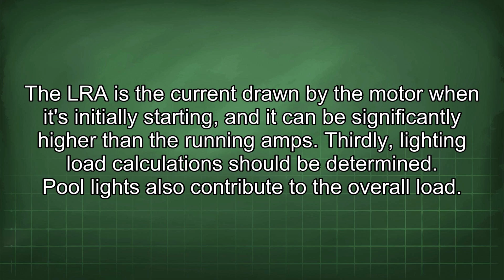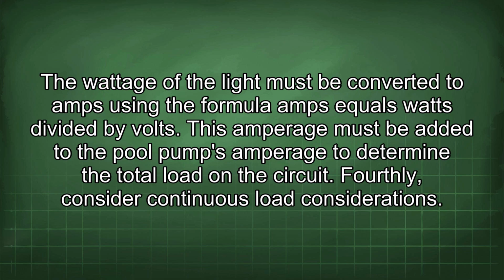the running amps. Thirdly, lighting load calculation should be determined. Pool lights also contribute to the overall load. The wattage of the light must be converted to amps using the formula amps equals watts divided by volts. This amperage must be added to the pool pump's amperage to determine the total load in the circuit.